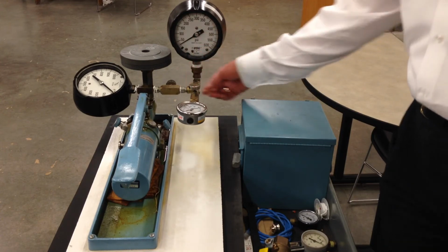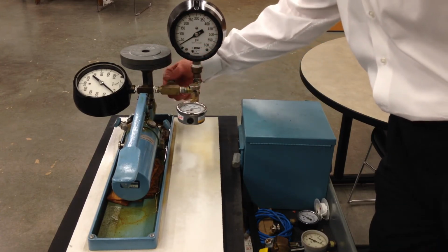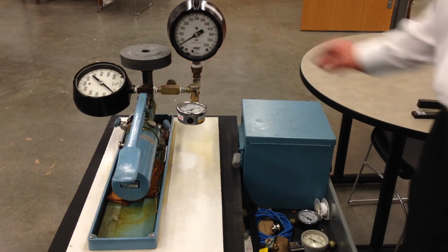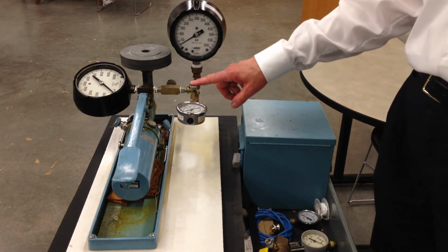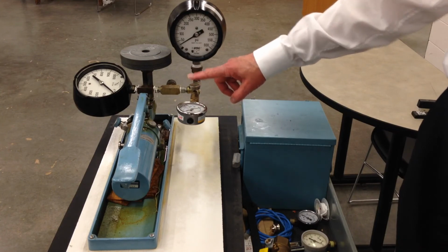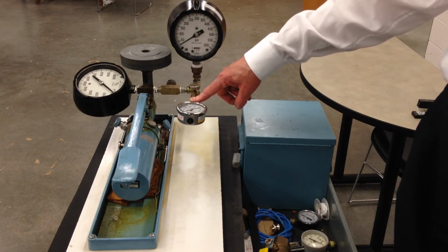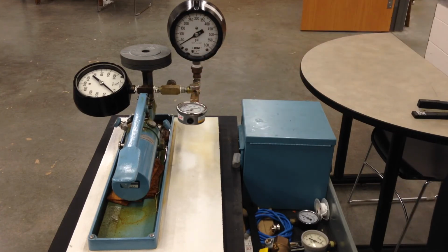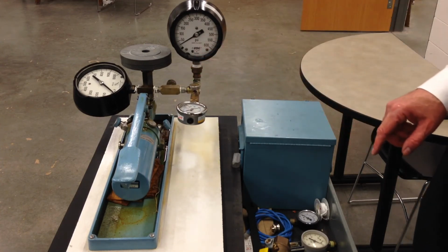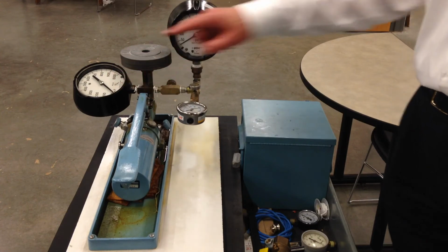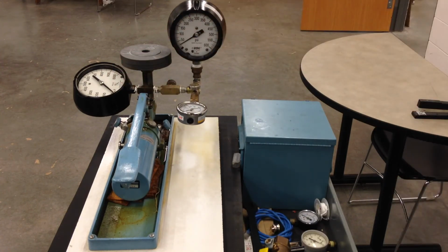And these needle valves are currently in the open position, or they're about to be in the open position, let's put it that way. When I get to 300, I'm going to close this valve, and this is going to be isolated from the system. Then when I keep pumping up to 600, I'm going to close this valve, and this gauge will be isolated from the system, and I'm going to take it all the way up, or at least as far as it'll go, to 1,000 psi. I have the dead weights to do that.